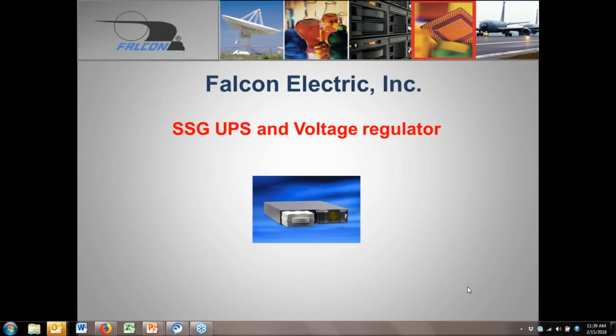Okay. Because another question, since you don't have a BMS on the battery pack or on the lithium pack, does the UPS recognize that it's charging a lithium pack versus a lead acid pack and use a different charging profile? Actually, the protection is built into the batteries individually. So inside the battery pack, there's 4 batteries. Inside there's the cells and the protection board. That board is protected against short circuit. It does have a cell balancing circuit inside. However, it doesn't have a communication port or anything like that.